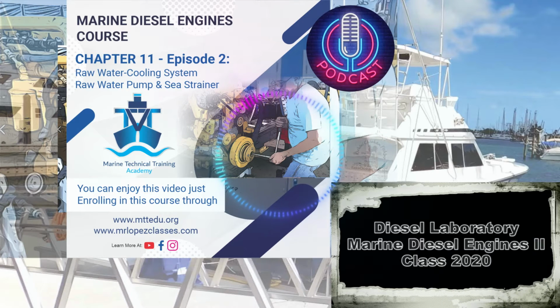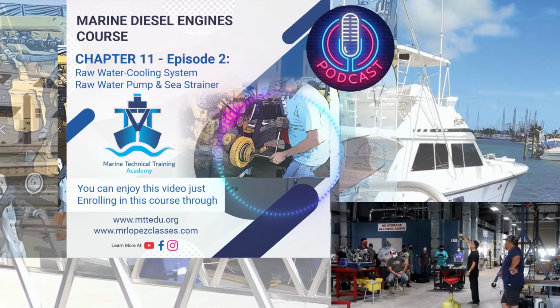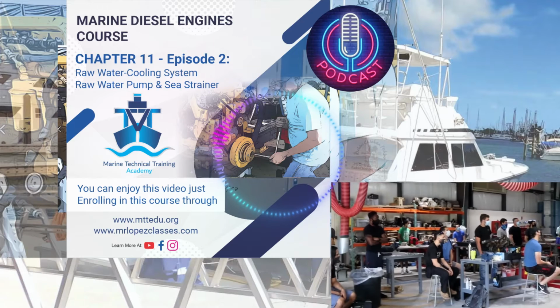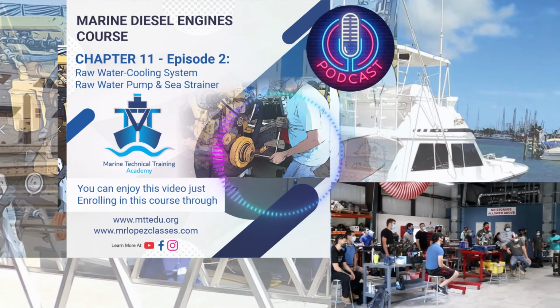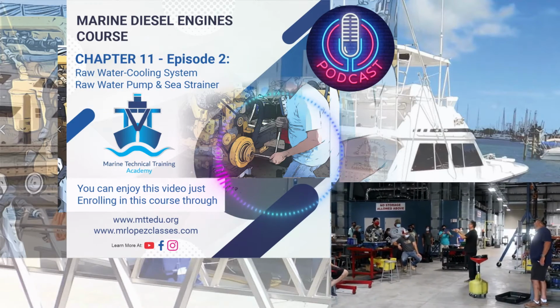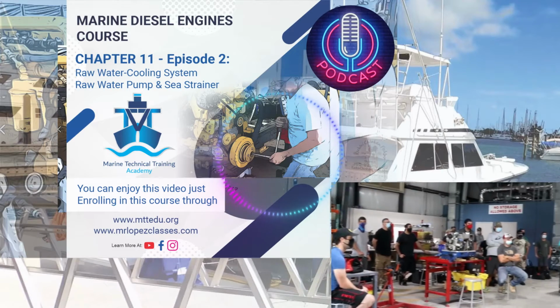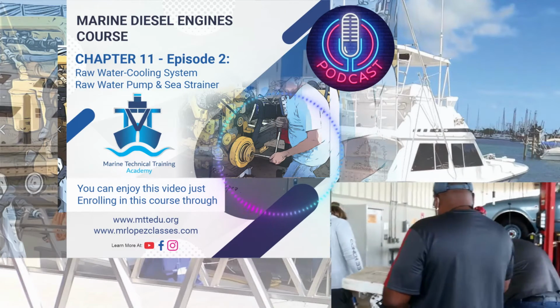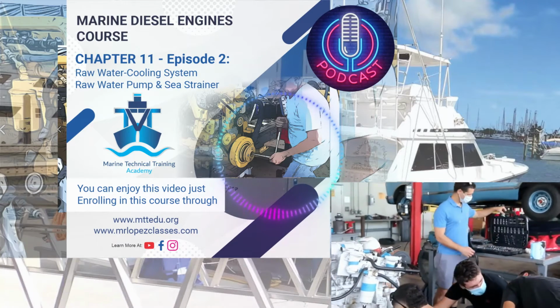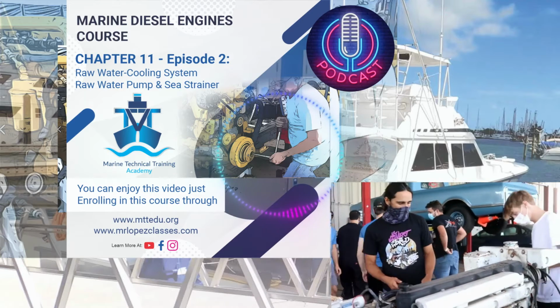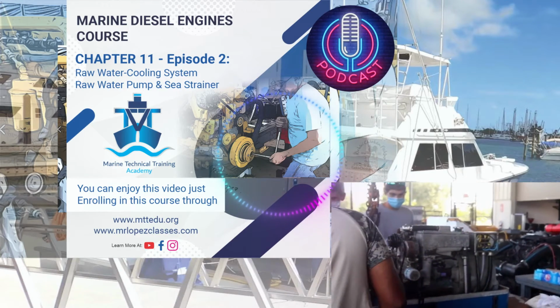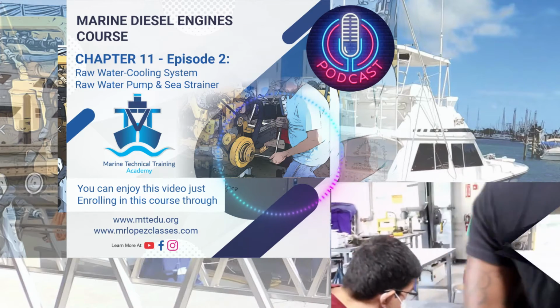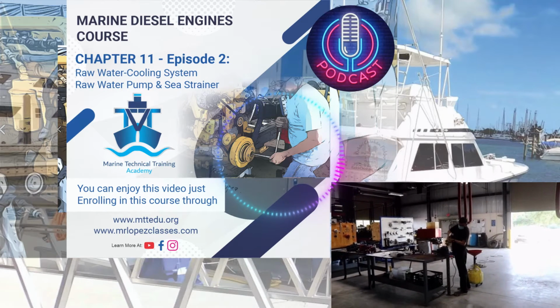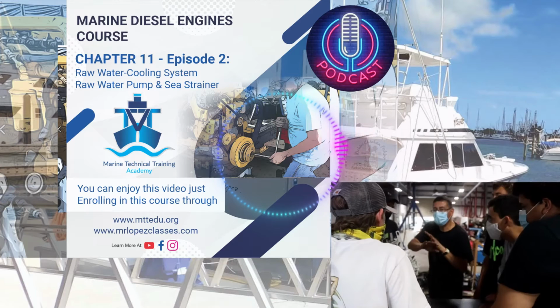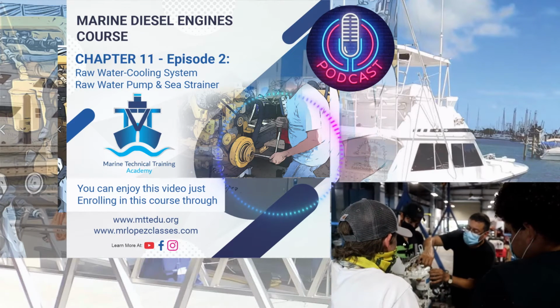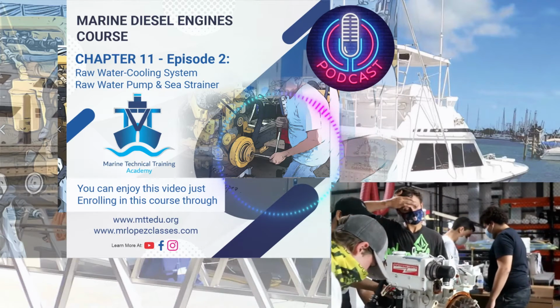All right, and yes, the most important part is where the limit of the water line is located. Where is the water line located? Because depending on the water line, the raw water pump and the strainer can be installed below the water line. This is the recommendation. They should always be installed below the water line, because it doesn't matter if the manufacturer of the raw water pump says that the pump is self-priming, I don't recommend it. I recommend installing the raw water pump, of course, and the strainer below the water line, in order to avoid that the pump runs dry and burns the impeller. This is the enemy of the impellers in a raw water pump.